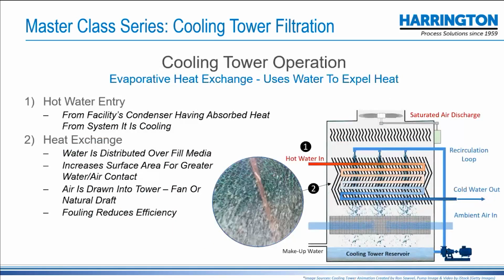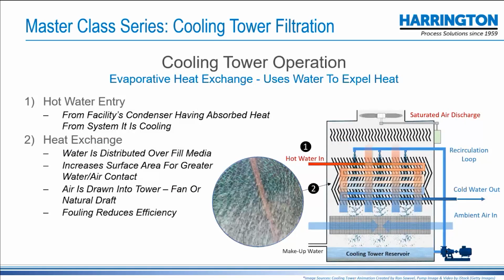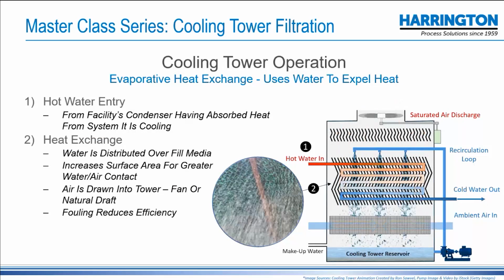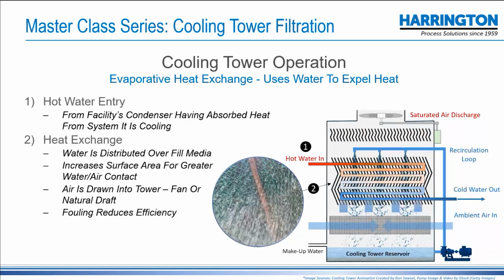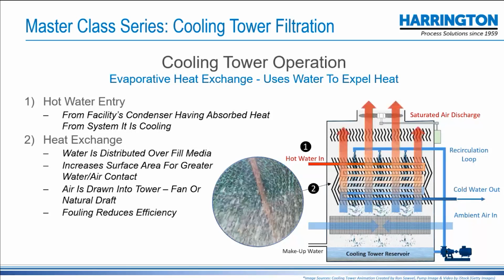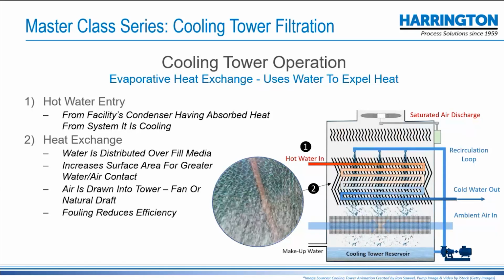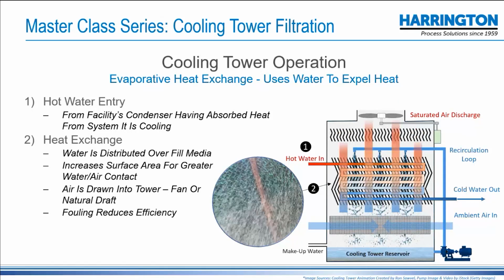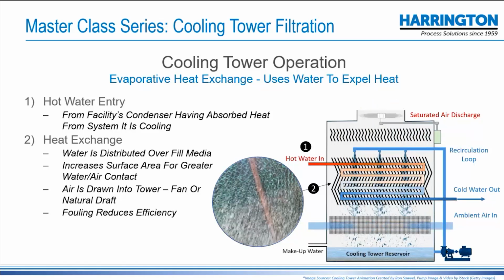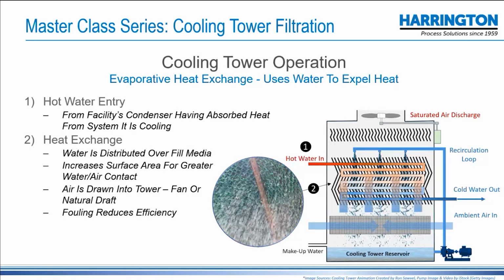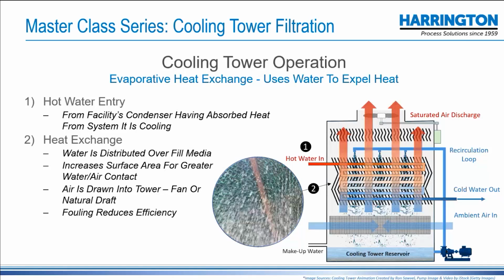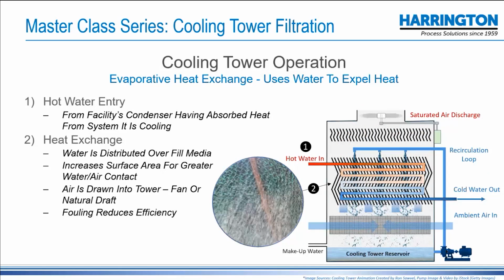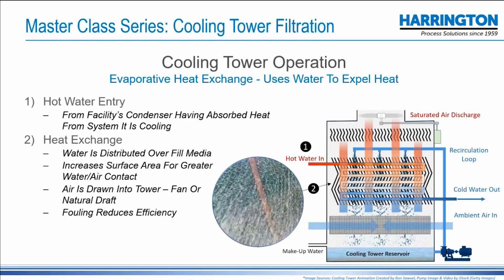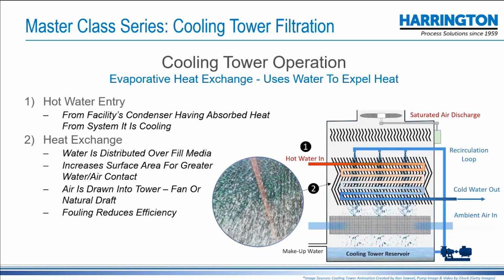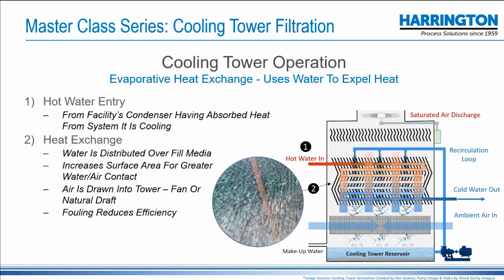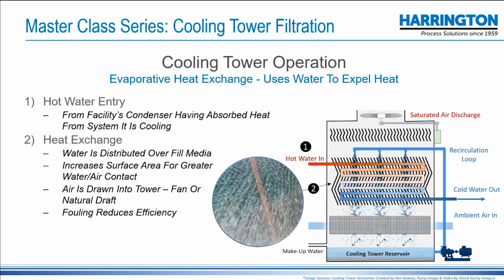And so how the system operates, you have, as I described already, hot water comes in. Now I'm only going to show the closed loop system going forward, but the hot water comes in and the water coming down over it through the dispersal elements from the spray nozzles is cooled by heat exchange via evaporation, and it cools that water for future use within the plant. And then falls through the reservoir.